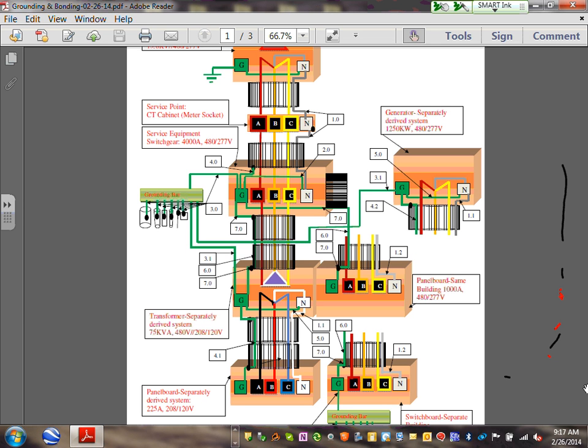Okay, so just to summarize, guys, what we have done, Adam: we started by going to the service, and we did grounding and bonding at the service. Then number two, we did grounding and bonding on a sub-panel inside the same building. Number three, we did grounding and bonding at a panel in a different building. Number four, guys, we did grounding and bonding at a separately derived system transformer. And number five, we did grounding and bonding at a separately derived generator.